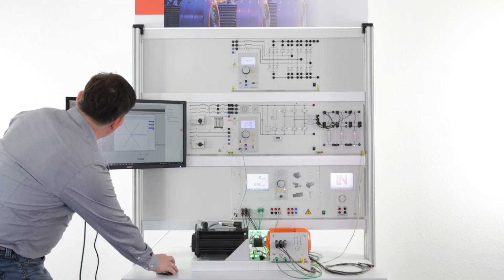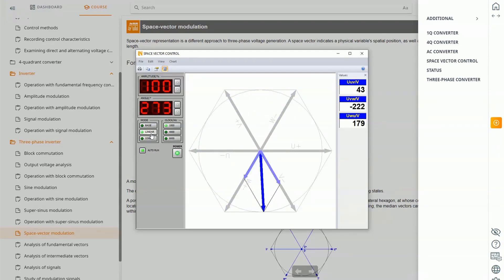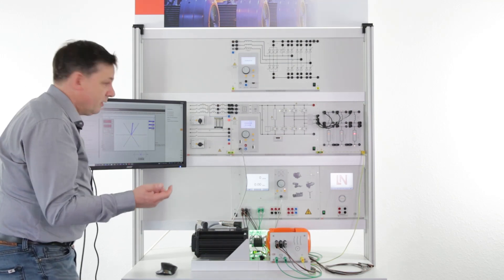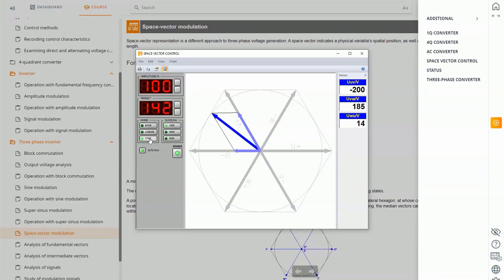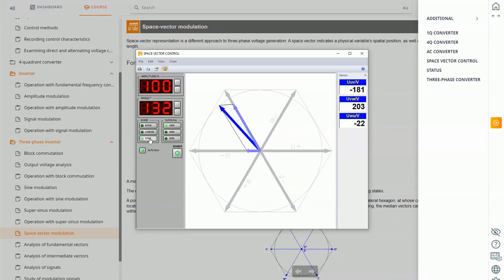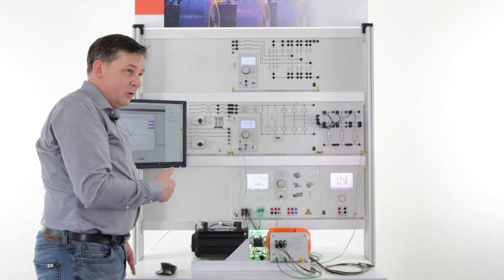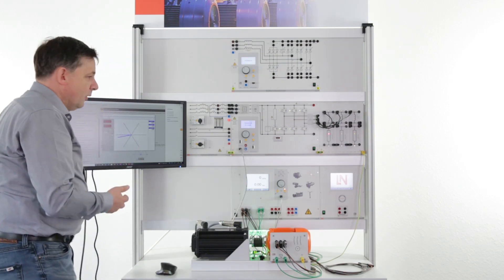Now we try the next step to make it more smooth. We go to linear, and now the system behaves linearly. In this case, we have the problem that the resulting vector is getting smaller and bigger — this causes interference into the motor, and the motor will not run smoothly. So the last step is to set it to sine. Now we can rotate our vector on the circle, and the motor can run very smoothly. That's the principle that almost all new systems use — even in automotive and in industrial frequency and servo converters.